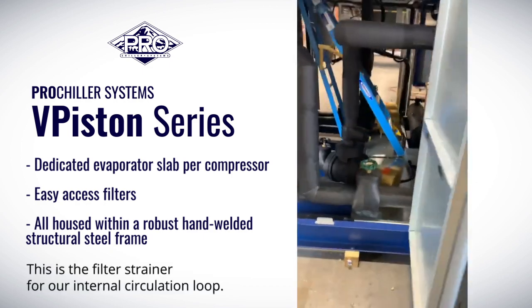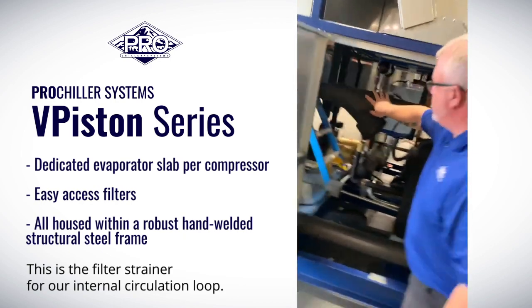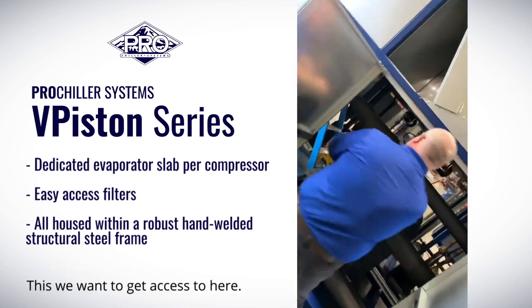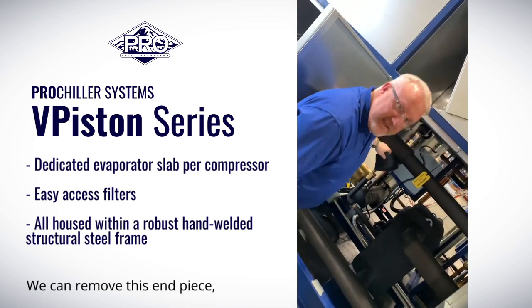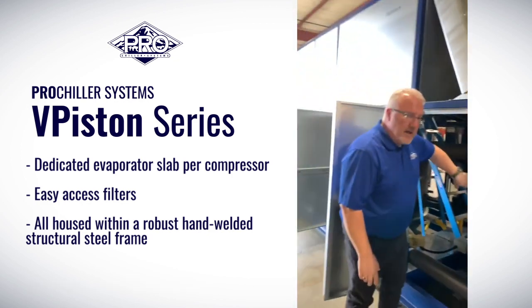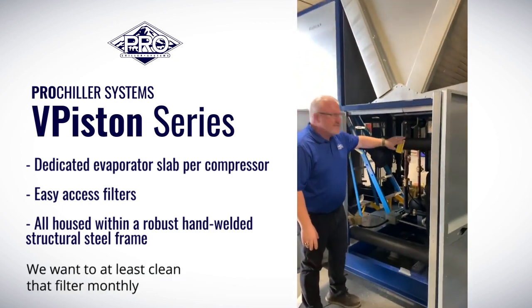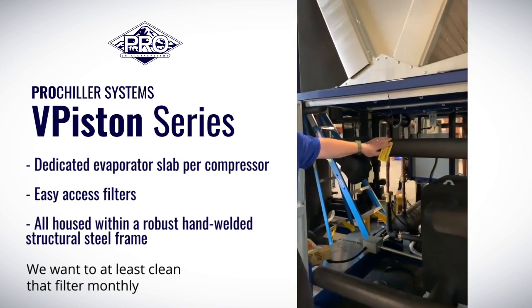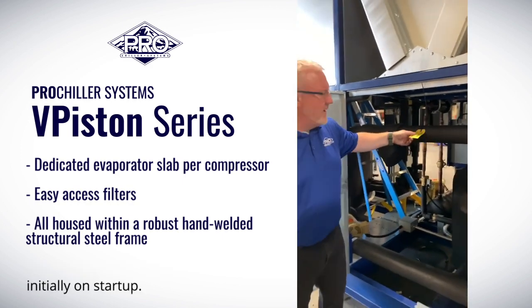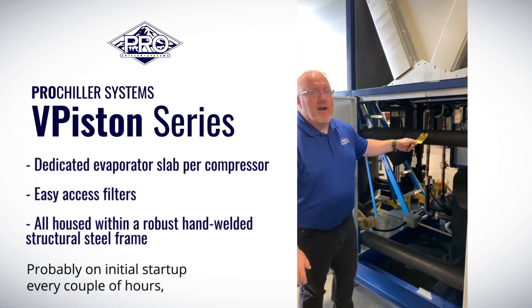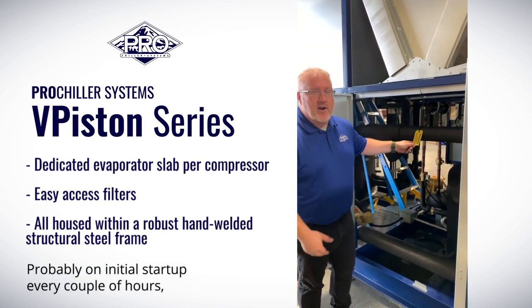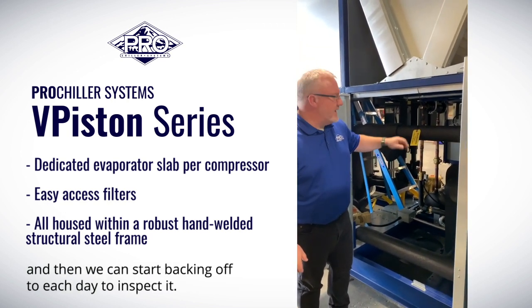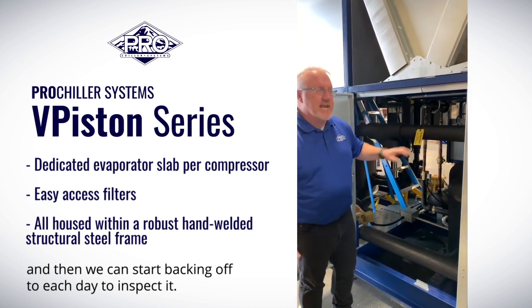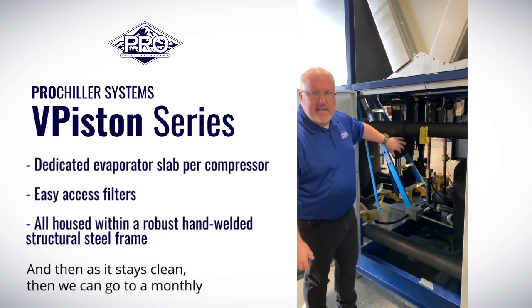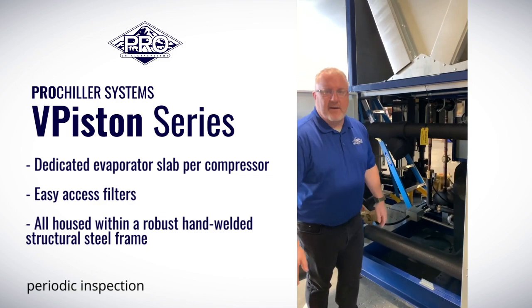This is the filter strainer for our internal circulation loop. We want to get access to here, so we can remove this end piece. Look at that filter. We want to clean that filter at least monthly. Initially on startup, we're going to clean this more often, probably every couple of hours, then we can back off to each day to inspect it, and as it stays clean, we can go to a monthly periodic inspection.